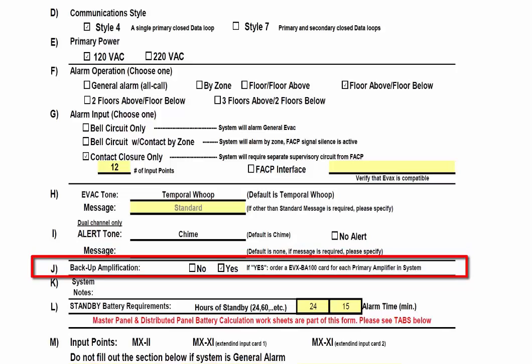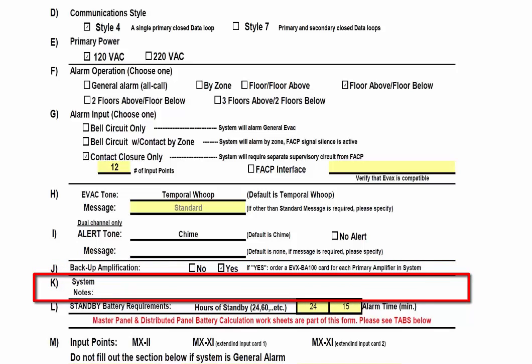Item J, Backup Amplification. Choose yes or no if you would like backup amplification for each primary amplifier on the system. If you choose yes, you will need to order an EVX-BA100 card for each primary amplifier on the system. System Notes is where you can put specific notes regarding your EVAX panel, such as the projected install date or the type of speaker to be installed on the system.